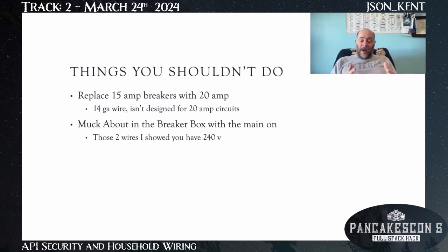But what happens with a lot of these circuits is you add and add and add to it over time. And then one day you flip the switch on for a half hot or something else, right? And it blows a breaker or causes some kind of problem. Had a really close friend that had a 15 amp breaker go bad. It tripped so many times it went bad. And so what was his solution? Get a bigger breaker and put that in.